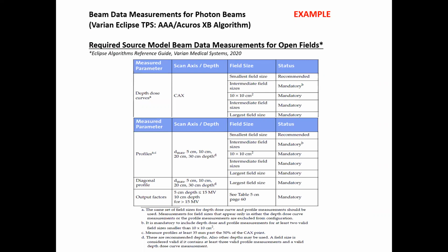This is just a typical example, courtesy of Varian Medical Systems, of beam data requirements for the AAA or the Acuros algorithm. I am showing this slide so that you can see all the specifications the vendors require for the beam data for the algorithms. What is the rationale of commissioning beam data? We can have a golden beam data.